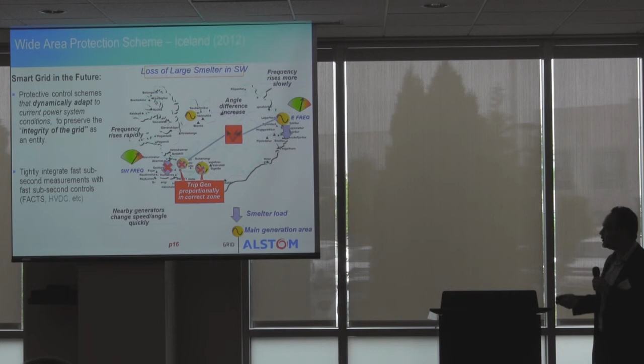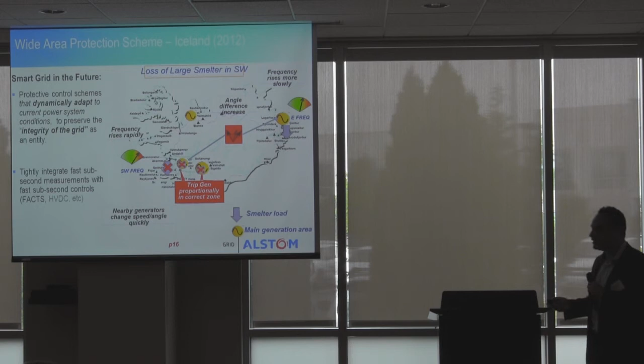The holy grail for this technology is wide area protection and control. We're doing this in Iceland with colleagues at Scimetrics, and the Icelandic system is quite simple, a radial system with a lot of generation on one side and load on the other. The scheme we've implemented is one where, if there's loss of a large load, the frequency changes naturally, faster on one side than the other, creating a large angular separation that's temporary. By wide area monitoring, we know whether it's truly an out-of-step condition or a lost smelter load, and we decide to trip generation accordingly. So by taking measurements across the grid, we are preventing instability in the system.